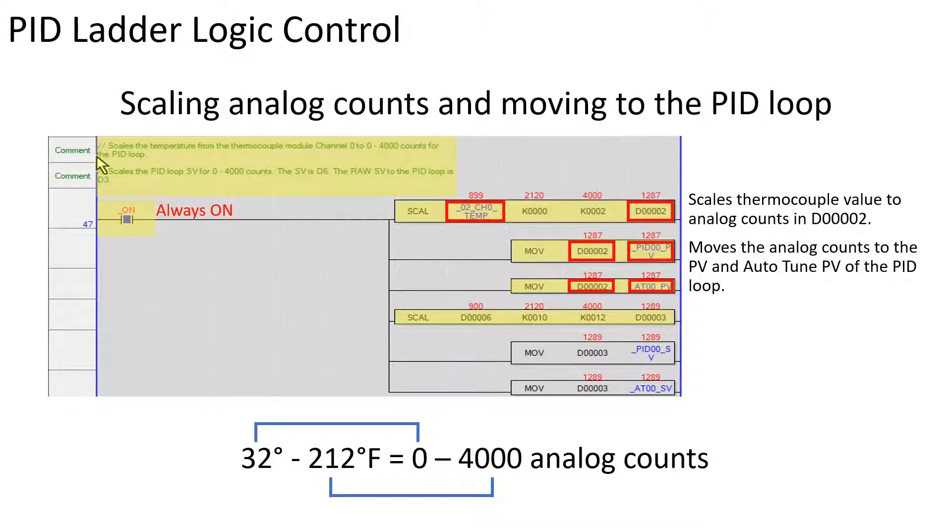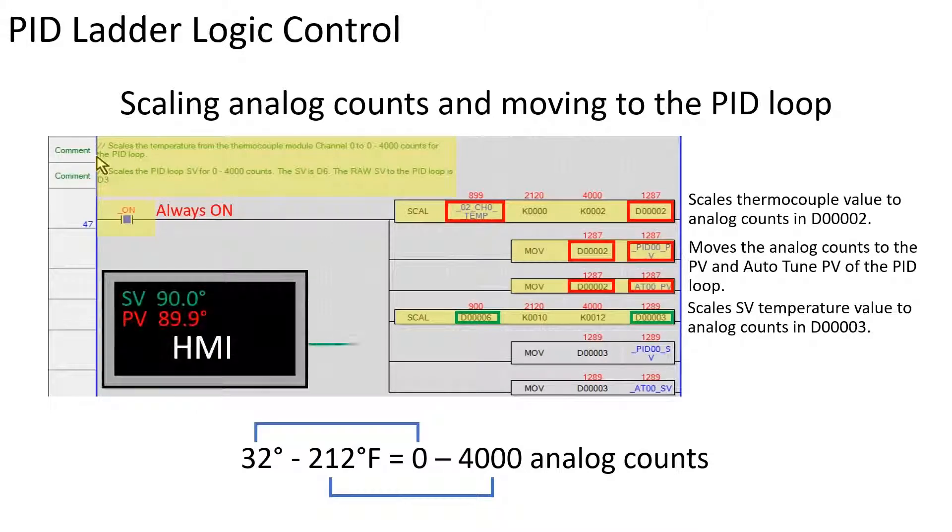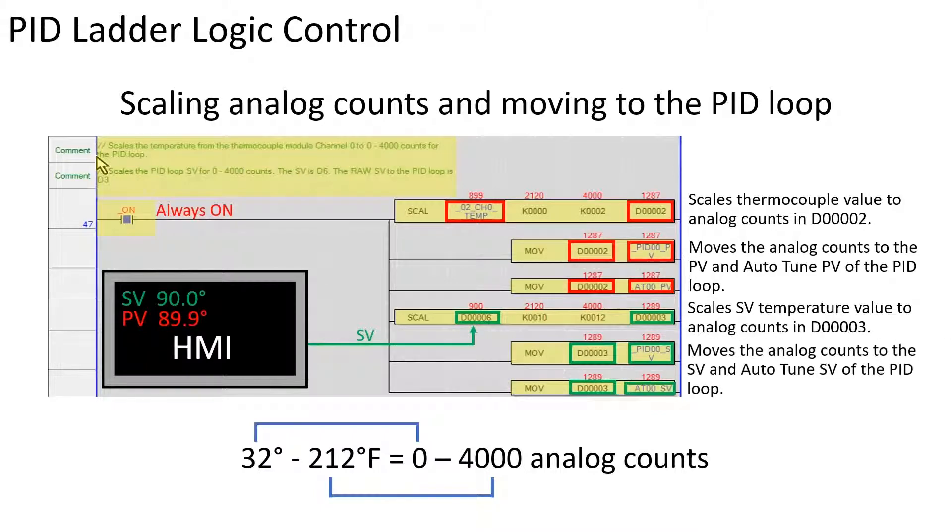The next instruction scales an SV value of 90 degrees in memory location D6 to location D3. D6 is the location an HMI would write to when entering a set point value. The scale data in location D3 is moved to the PID operation SV and autotune SV.